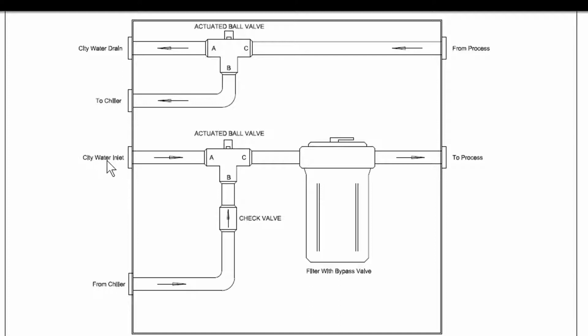So on the opposite end of your city water inlet, you have your city water drain. This is typically drained off to some type of a floor drain in the equipment room. You want to make sure that that drain is capable of providing enough flow rate. I always recommend a commercial industrial type of drain. That way, if that drain plugs up, you're not going to flood your building. So that's a really important thing. You have your line here coming from your chiller. So this is the line coming from your process chiller. And then, of course, you have your line going back to your chiller, right?